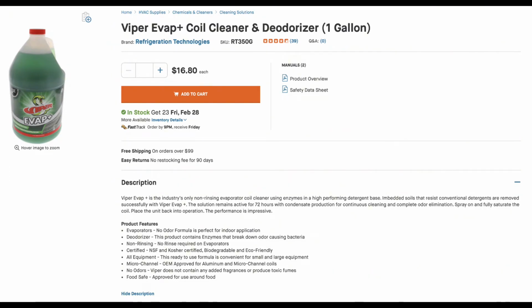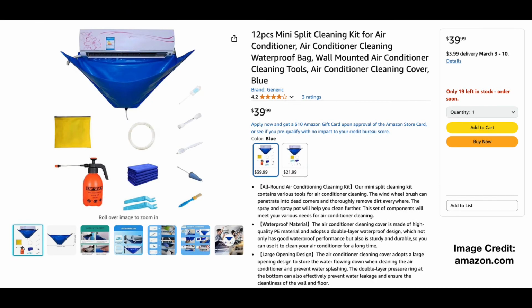Here's an example. And I would recommend one of these mini split cleaning kits, or sometimes referred to as a bib kit. It comes with this catch bib that would catch the water as you spray down your evaporator coil with water and you spray off your blower wheel with water inside that head unit. It'll catch the water, and then you could direct it into like a 5-gallon bucket, for example. You'd still want to put down a tarp on the floor. This kit will make it so that you try to eliminate getting the floor wet or the wall wet.